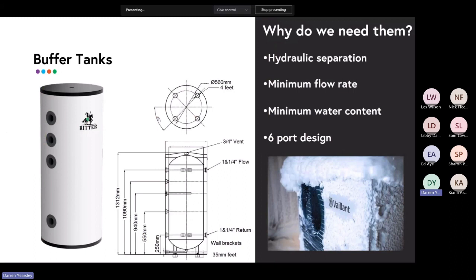Okay, so some of the other components which we put into these systems hydraulically, these are indirect appliances. So this is mechanical water which we're putting through the heat pump. We're not running potable water directly through. Typically with CO2, they are direct, so they have potable water going through them. One of the limitations of that, and the reason why they do that, is because they're always trying to optimize the delta T. They're trying to get that single pass operation going as efficiently as possible. So if you can send cold water from the street directly to the appliance, then that's their happy place. But because we're operating on multipass and we're quite happy with warm water going back to them, these appliances are only for indirect application.